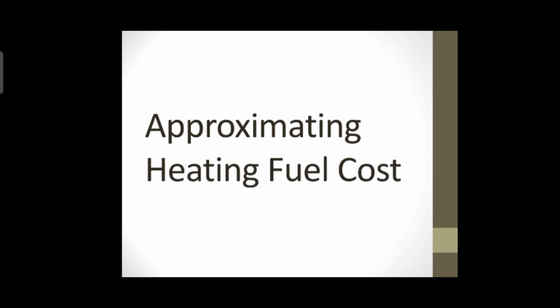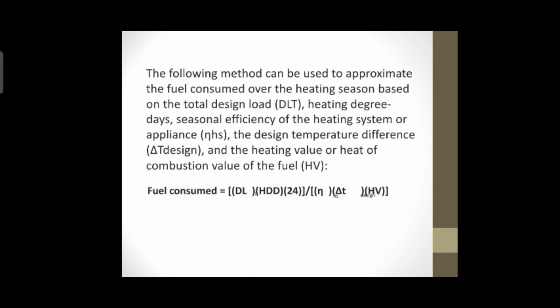So approximating heating fuel cost. The following method can be used to approximate the fuel consumed over the heating season based on the total design load, heating degree day, seasonal efficiency of the heating system or appliance, the design temperature difference or delta T design, and the heating value or heat of combustion value of the fuel. So we're gonna have here fuel consumed is equals to DL sub T or the total design load, and then multiply it to HDD and then multiply to 24, all over N sub HS or the heating system or appliance efficiency, multiplied to design temperature difference or delta T design times the HV or the combustion value of the fuel.